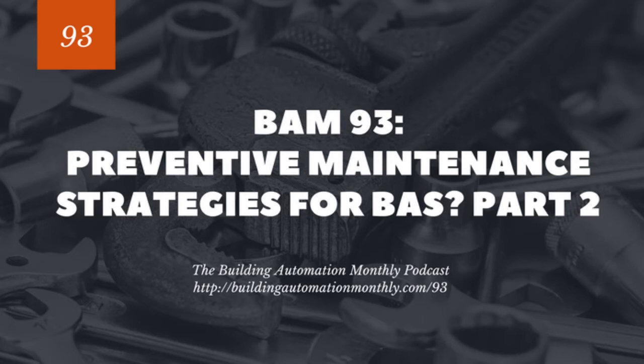they get device conflicts. And BACnet's a lot of things, but what it's not really good at is natively telling you what's wrong. Meaning that it really depends on the manufacturer to implement error codes and things like that for you to figure out what's wrong. And some manufacturers do that quite well, some not so much. And because of that, I find a lot of folks with network ID and instance number issues, and the network is basically blinking. It's on, it's off, it's on, it's off. Or sometimes it's just very flaky, it's very slow, and they can't figure out why.